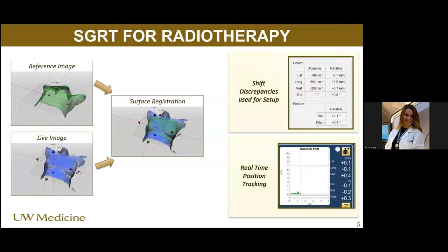What does that mean for radiotherapy? In radiotherapy, we want our patients to be in a specific position because we plan a whole treatment based on that one position. The goal is to have a reference image of our patient in treatment position, and then compare that to a live image of our patient on the treatment table. A registration occurs where the system overlays the reference image to the live image, provides shift discrepancies, and we can use this for setting up a patient and for real-time persistent tracking throughout the duration of their treatment.